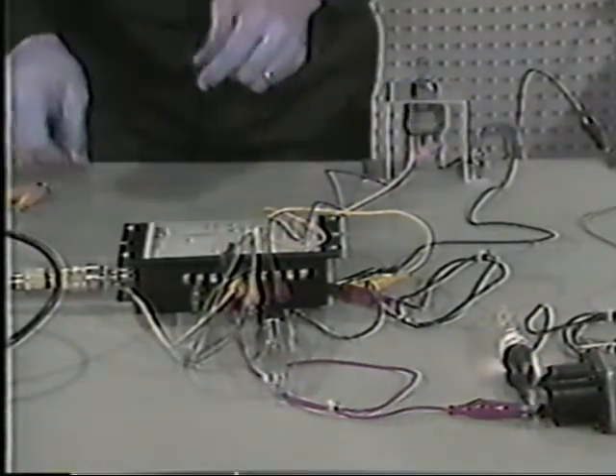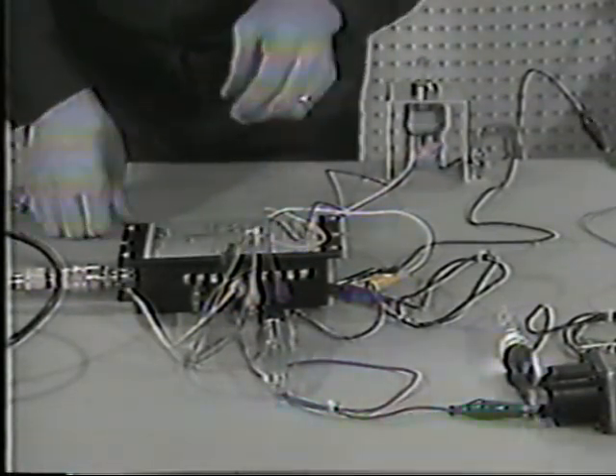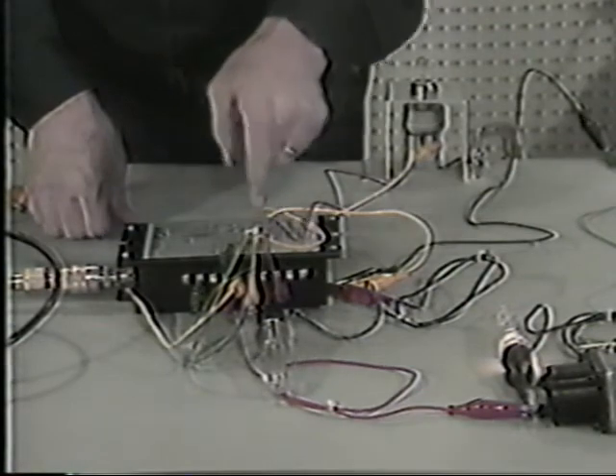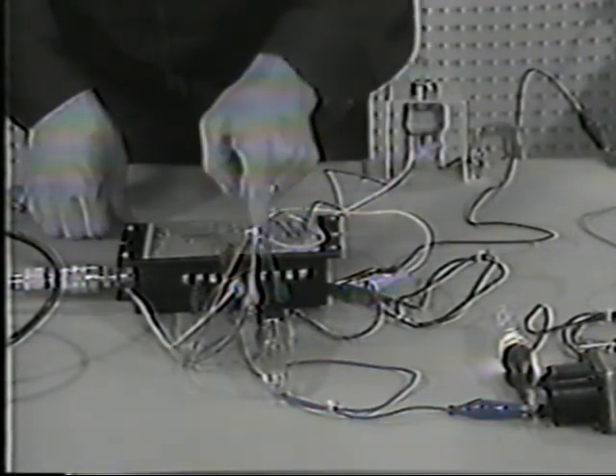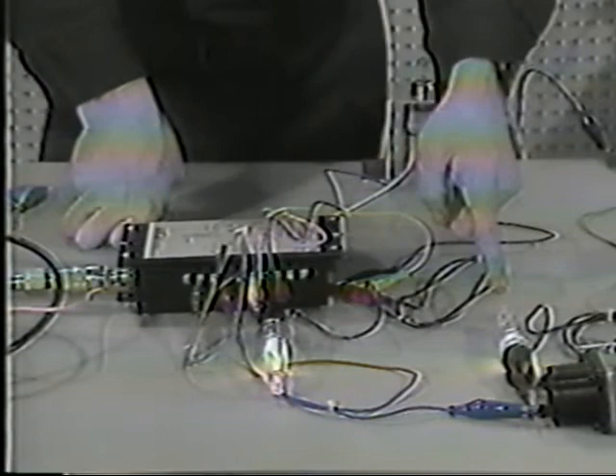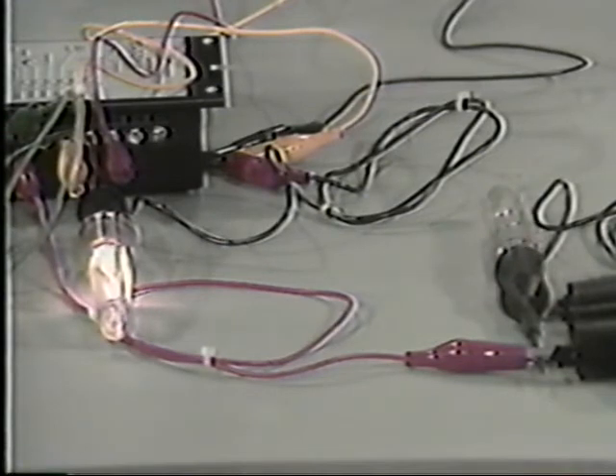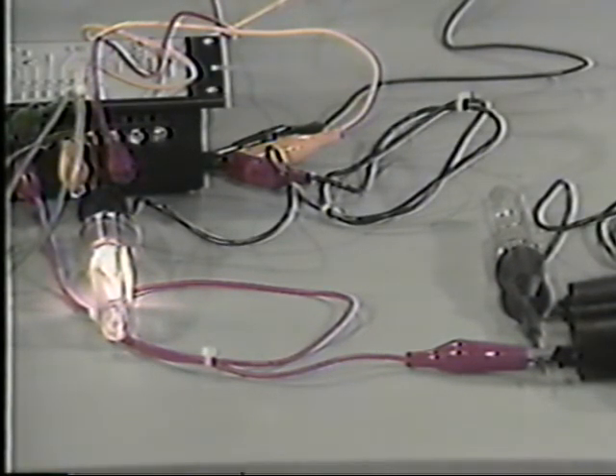Last test. Disconnect the wire to the water terminal, which is the 5th one down. As soon as you do this, the warning test light should come on, the fuel solenoid test light should remain on for 20 to 40 seconds and then go off. And in this case, the test passes. Any module that does not pass all of these steps has an internal problem and should be replaced.